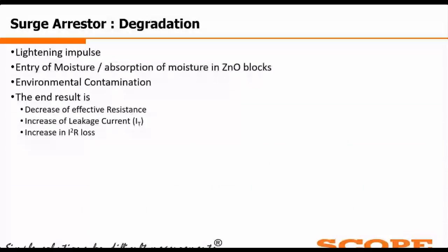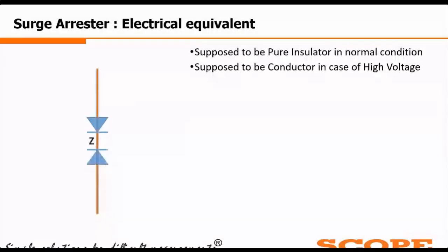So when the degradation starts, the effective resistance in the healthy condition decreases. We can understand that if the resistance is decreasing, then the leakage current through the LA will be increasing, because there is a live connection at the top and the grounding at the bottom, so there is a path available. So the leakage current flowing will increase, and as a result we get higher I square R loss, a lot of heat generation in the LA, and it will go for failure.